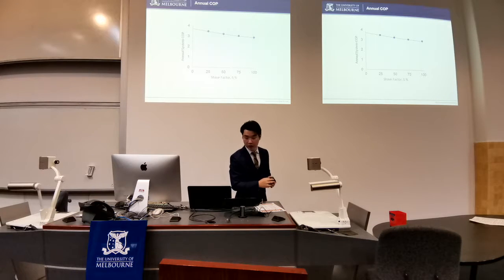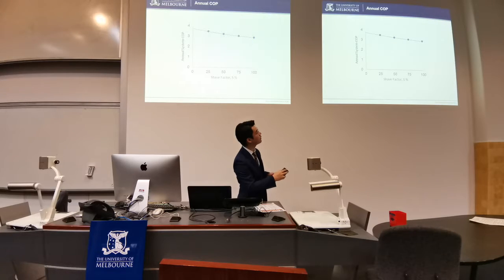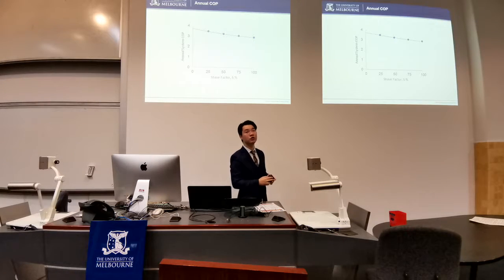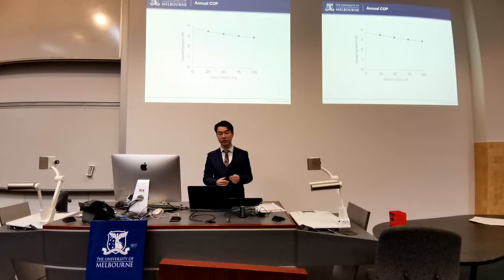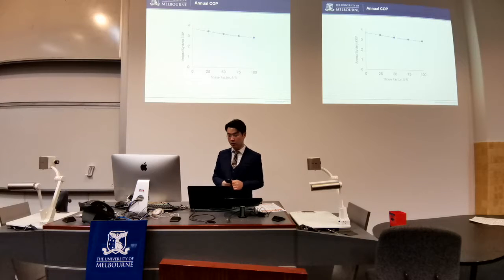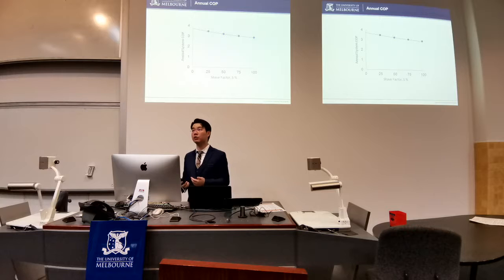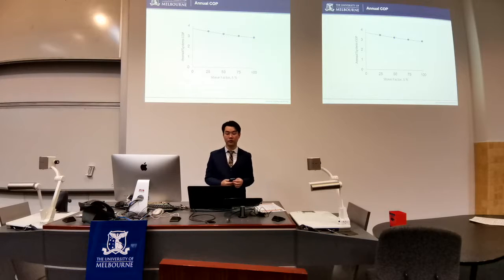It's a bit counterintuitive, but when you install a higher capacity system, the COP tends to decrease. That's because when you install higher capacity, or when the load isn't that high, you could expect partial loading of the heat pump, and under partial loading, its efficiency can go down.